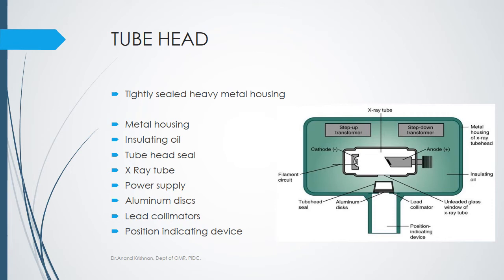The tube head has a very tightly sealed heavy metal housing coated with lead to prevent x-ray scattering and converge it to one point. It contains insulating oil which also acts as a coolant, because a lot of heat is generated in x-ray production. The tube also consists of step-up and step-down transformers. The x-ray tube — a vacuum tube or Coolidge tube — consists of the anode and cathode, along with aluminum discs, filters, lead collimators, and a position-indicating device.